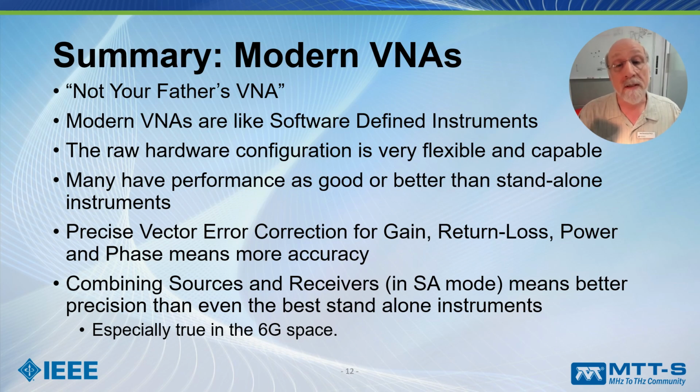So in summary, this is not your father's VNA. Modern VNAs are like software-defined instruments where you can reconfigure what they do based on the software you have, because the hardware is very flexible and has very high performance. In fact, the raw hardware is as good as standalone instruments. For example, the receiver in a modern VNA might have as low a noise figure as the receiver in a spectrum analyzer. In addition, because we can do precise VNA-style vector error correction on power, phase, gain, and return loss, we can remove a lot of systematic errors that standalone instruments have to live with in their measurement floor.